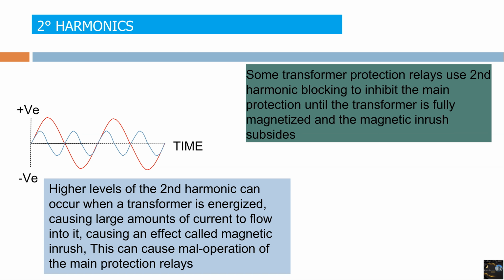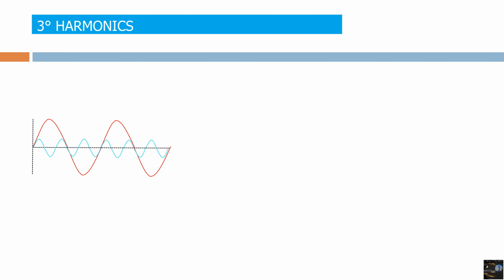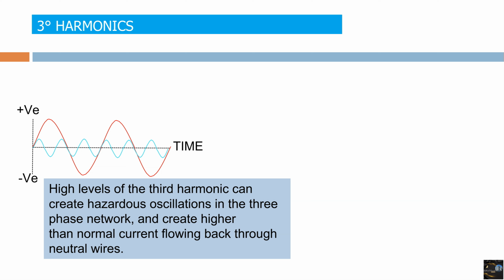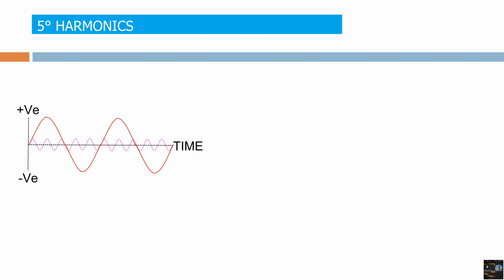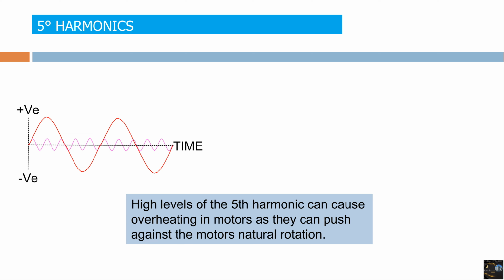Then comes our third harmonic, time versus voltage. A high level of the third harmonic can create hazardous oscillations in the three-phase network and create higher than normal current flowing back through neutral wires. Then our fifth harmonic. A high level of fifth harmonic can cause overheating in motors as they can push against the motor's natural rotation. As I told you, we will see these types of harmonics in our practical examples.